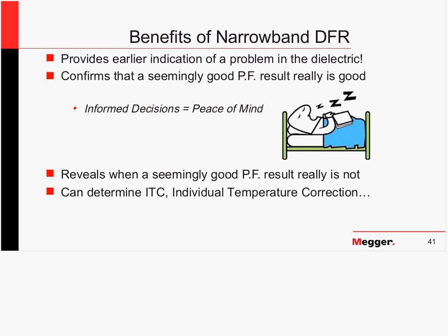Because I would tell you that there are some seemingly good power factor results that are not representative; they indicate the system's good when in fact it's not. So this testing confirms that, hey, the seemingly good power factor really is good. That informed decision gives you peace of mind, lets you sleep at night. It also will reveal when the seemingly good power factor, oh yeah, this looks good, no, it's really not good.